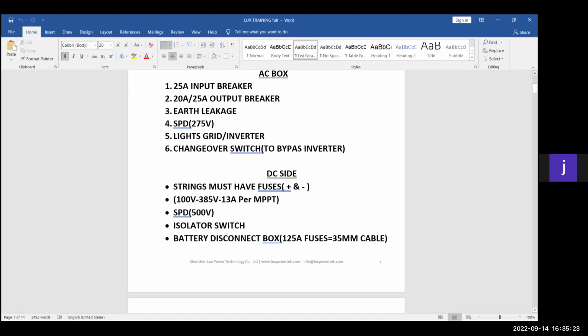Now, my output breaker, this is where I have a lot of clients that don't agree with me. That's more than fine. I try to put a 20 amp output breaker on the inverters. Now, the reason why I recommend a 20 amp output breaker is that the breaker will trip before you can physically overload the machine. At 20 amps, you have roughly 4.7 to 4.8 kilowatts, depending on certain factors, that you can pull out of the breaker before it physically trips. So that means that you can physically never get my inverter to go into EPS overload tripping. You will always trip the breaker first before the inverter physically trips.